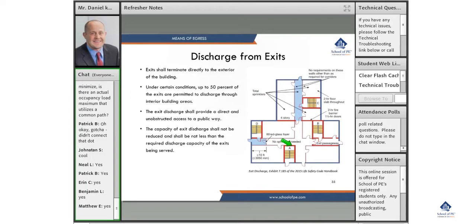You're allowed up to 50% to not be connected directly to the exterior. So you can see example C — you put it onto the corridor, and the idea is you go right onto the corridor, and then the actual exit — the exterior door — is visible. So you'll leave the exit, and then you can start walking, and this blue space is actually the exit discharge.